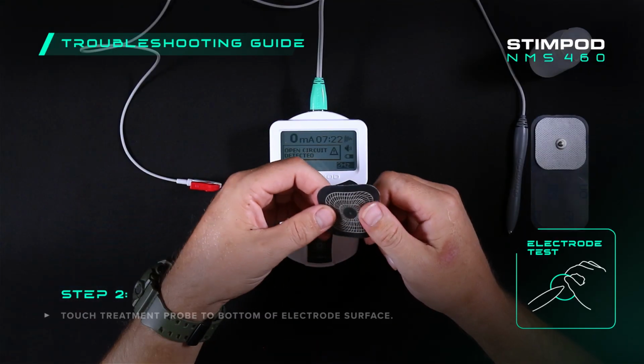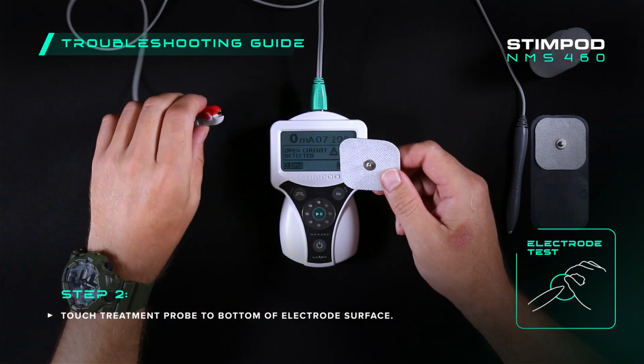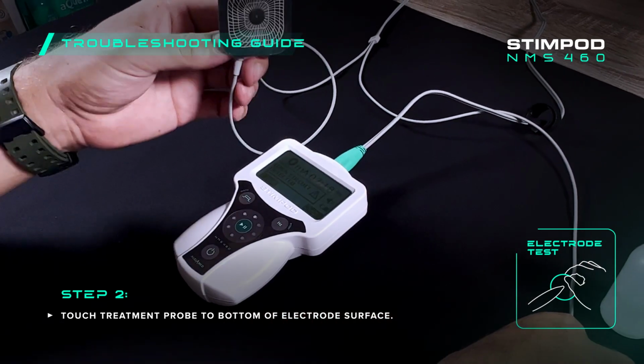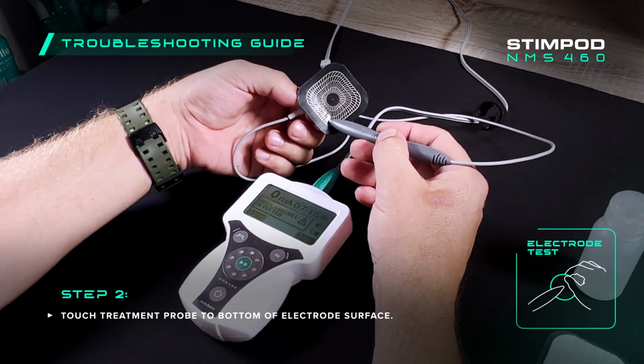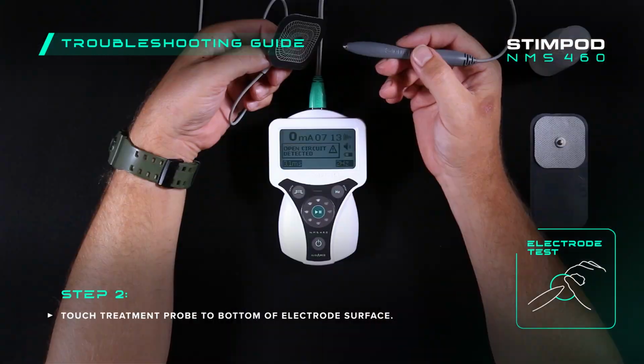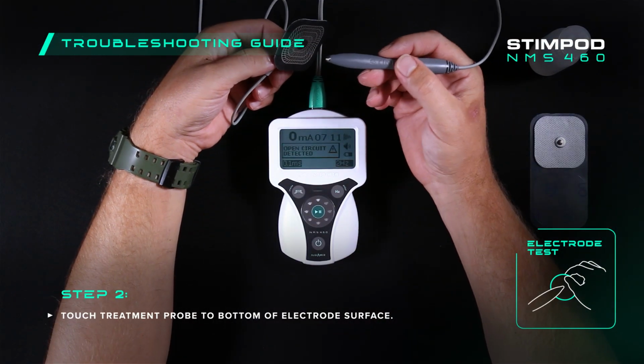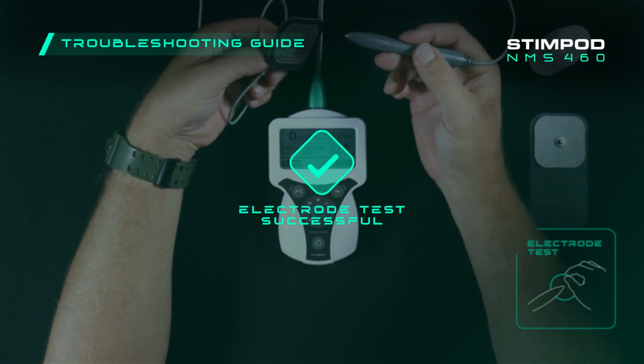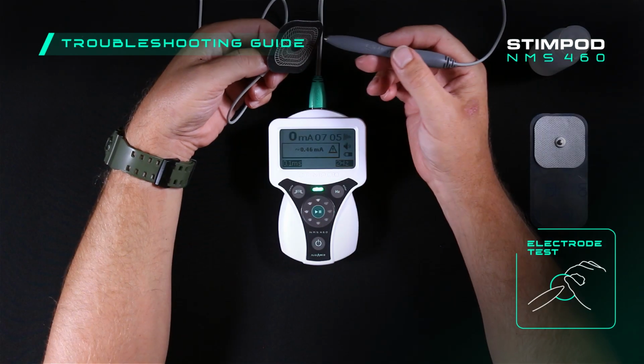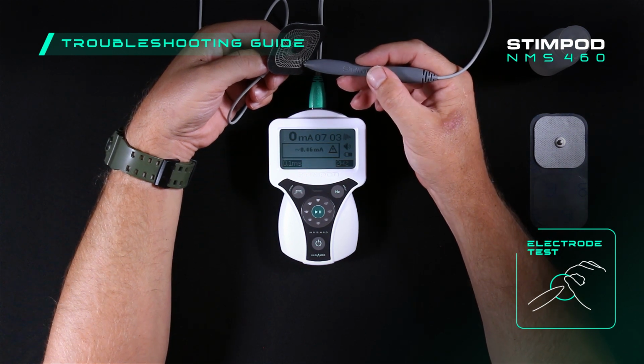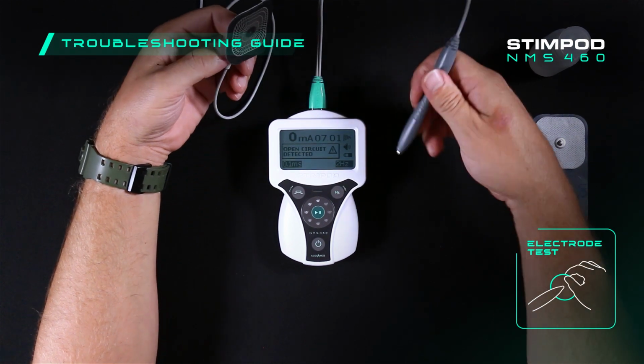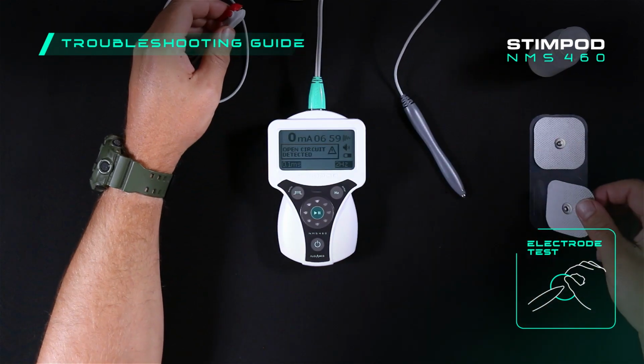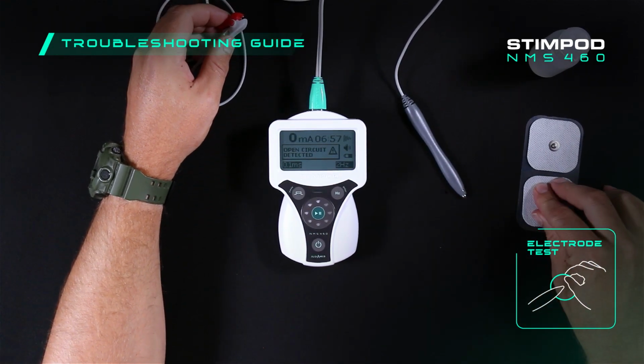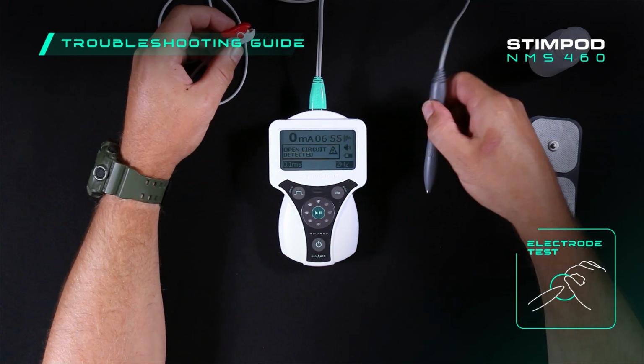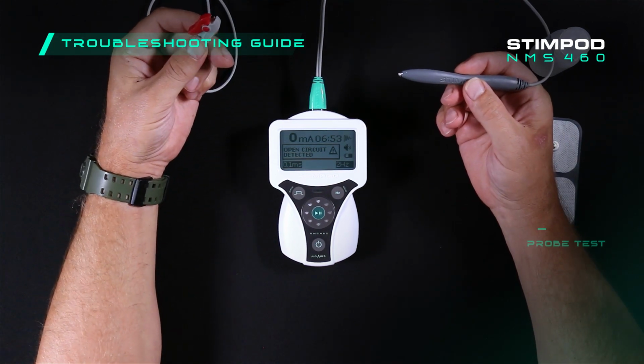You can now connect the cable's electrode to the metal nub and touch the treatment probe on the contact surface at the bottom. If the electrode is working correctly, the open circuit detected message will disappear and the Stimpod will display the current that is being delivered. You will also hear a beep sound for every successful stimulation delivered, and the LED will flash green. If the open circuit detected message is still displayed on screen, the electrode may be faulty and will need to be replaced.